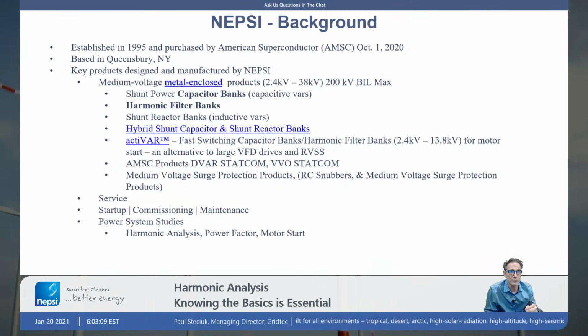We build capacitor banks, harmonic filter banks, shunt reactor banks for pulling in reactive power. We also have what's called a hybrid shunt capacitor shunt reactor banks that are very popular in the renewables area, where we sometimes need to consume reactive power because of the large collector systems used within.